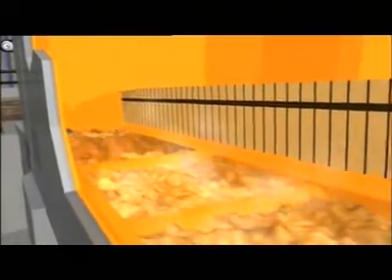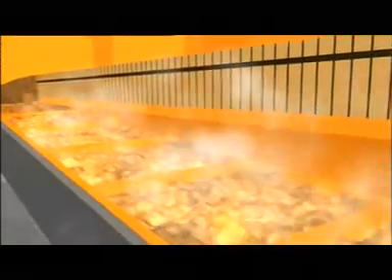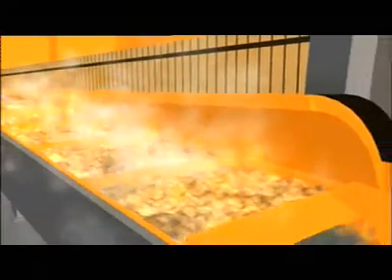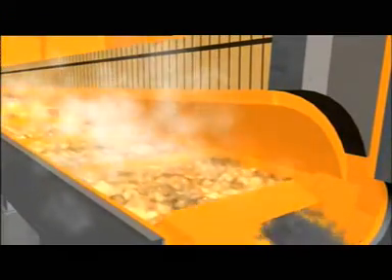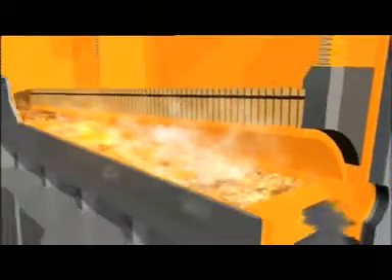Once in the primary chamber, the waste is turned into a syngas. The Energos control system ensures that partial oxidation, known as gasification, occurs in the primary chamber. So thorough is the process that by the time the waste reaches the end of the grate, the carbon has been effectively removed. This results in the production of a very low carbon ash.